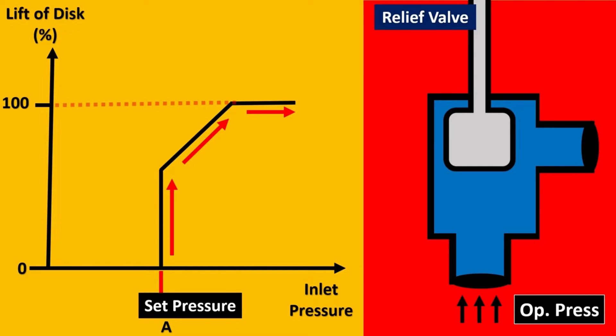At 100 percent disc opening the relief valve is fully open. Now let's trace back what happens as fluid exits through the relief valve — the pressure gradually reduces. Tracing this with a blue curve, you would notice something very interesting: at a certain point the set pressure is reached again, and ideally the relief valve should close, but it will not close.